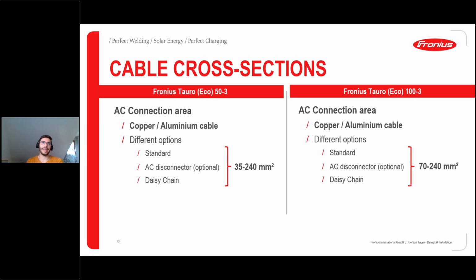Yeah, on the AC side, we do have recommendations for the cross section that you're using. Looking at the 50 kW device of the Tauro, you can use, of course, copper and aluminum cables on the AC side. That's no problem. You can use both of them. And it doesn't matter if you use a standard version, single or multi-core, or if you're choosing an AC disconnector or a daisy chain option, the minimum cable you should use is 35 square millimeters, going up to 240. And for a 100 kW device, again, you can use copper or aluminum. However, the minimum size here is 70 square millimeters on the AC side, because of course, double the current, double the power is running over this cable. So therefore, 70 to 240 square millimeters is recommended for the 100 kW device.